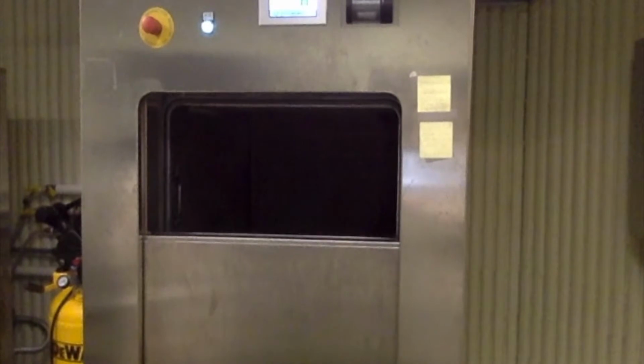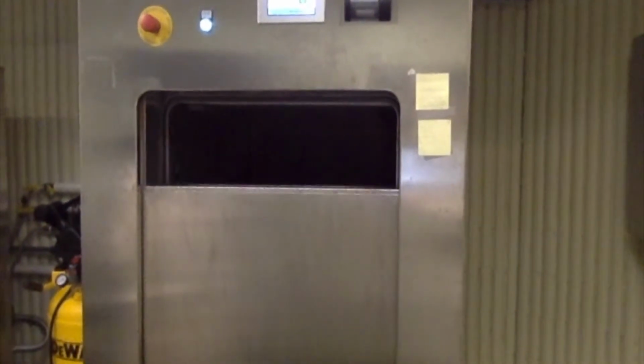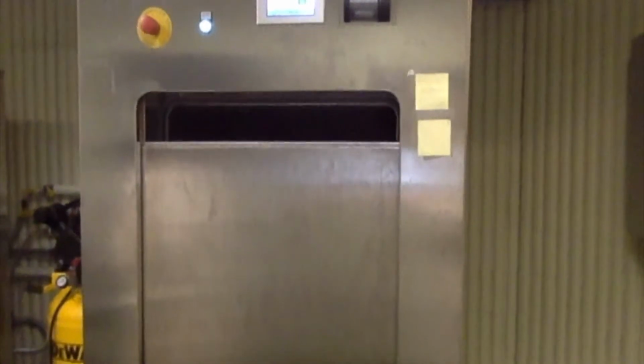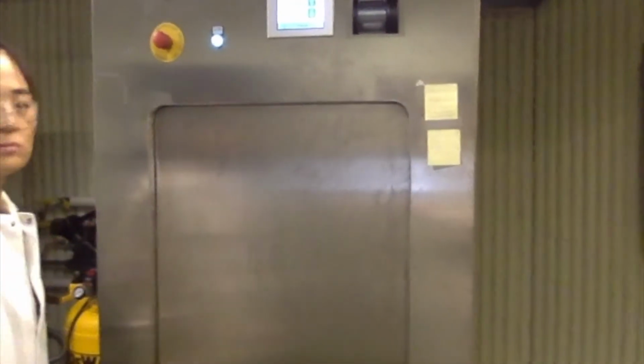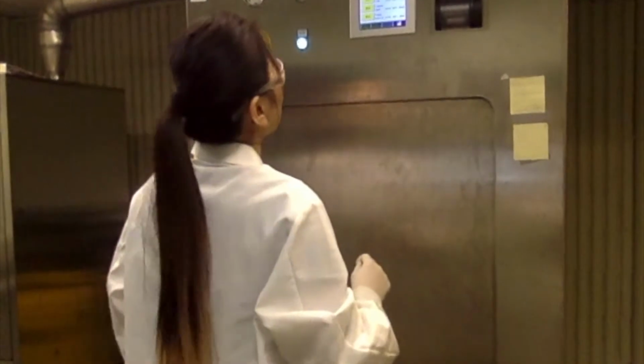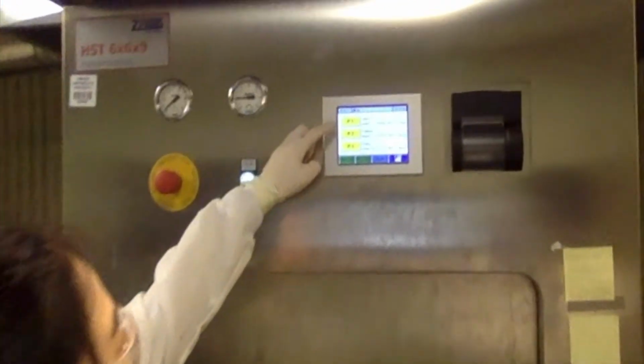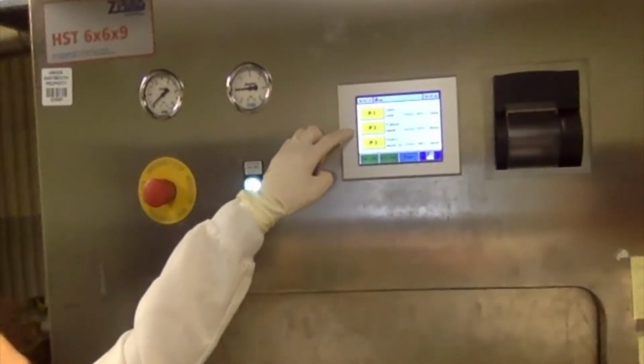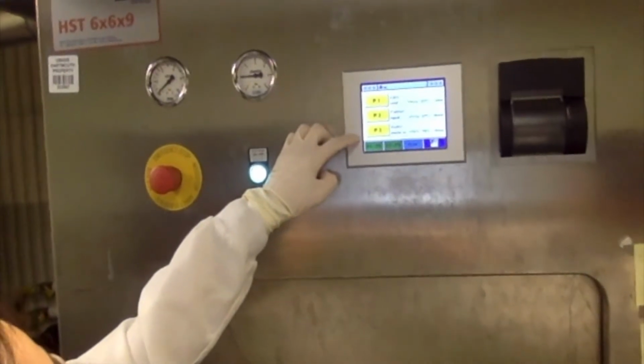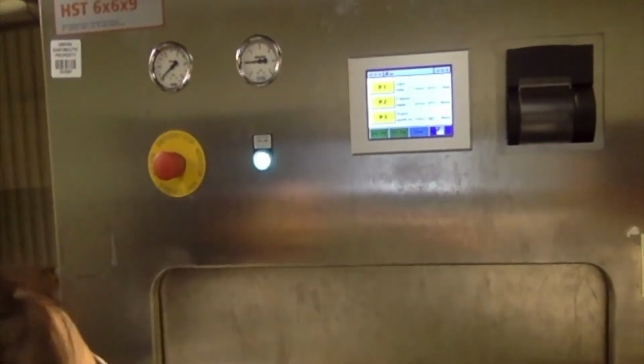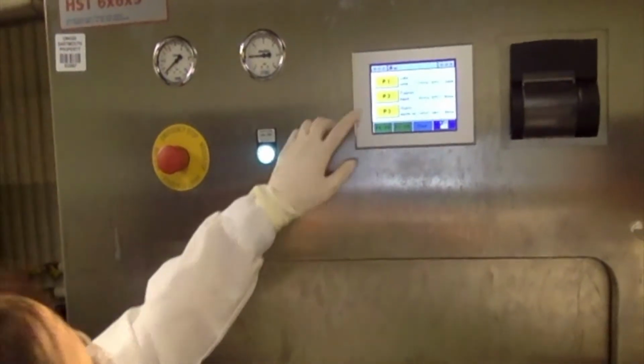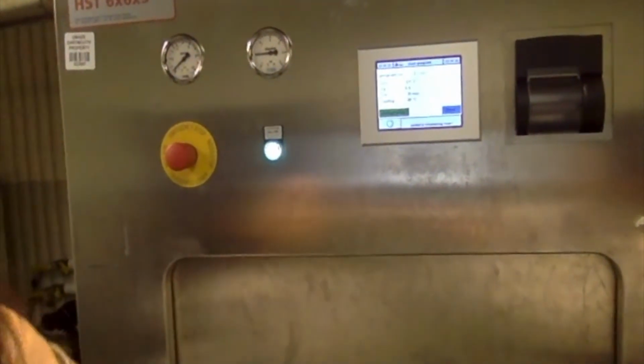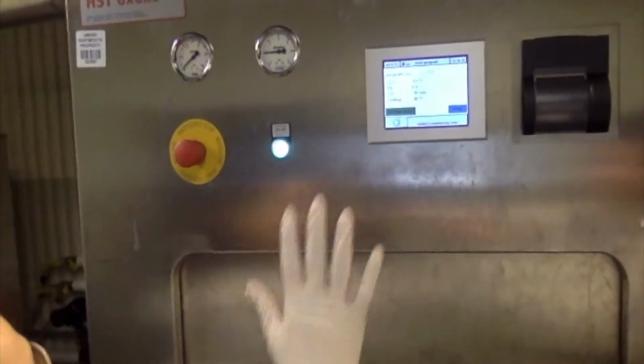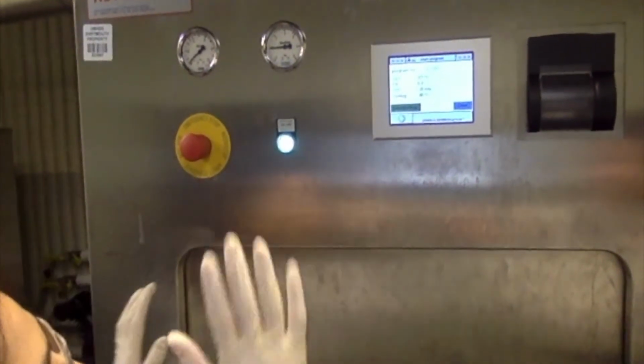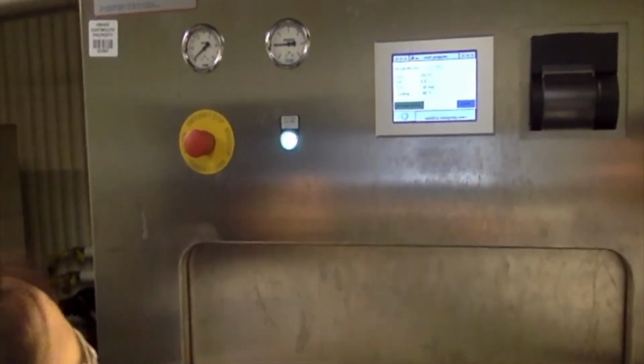An autoclave sterilizes the sample by high temperature and high pressure. Okay. So once you're done, there are 3 autoclave options in this machine. Usually dry is for solid and liquid is for anything wet, so you choose this option. The other one is waste. Now LB media is liquid, right? So we'll choose option 2, liquid. Once you push it, the machine itself sets all the pressure, temperature, time and cooling temperature.